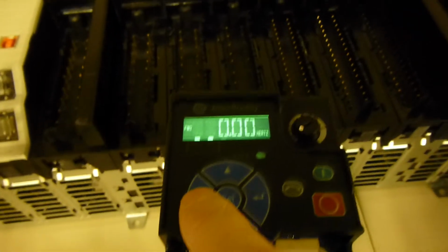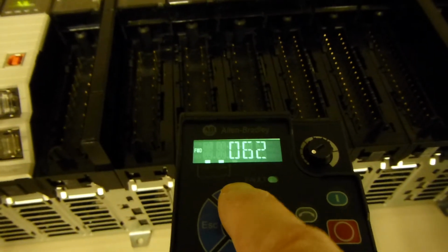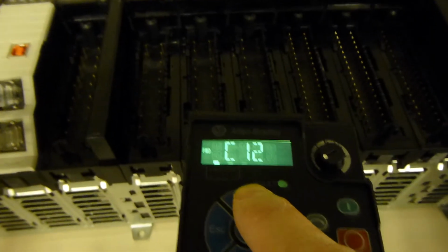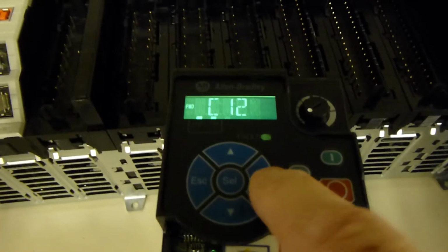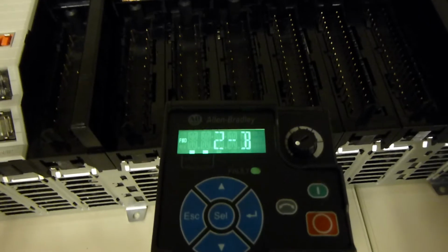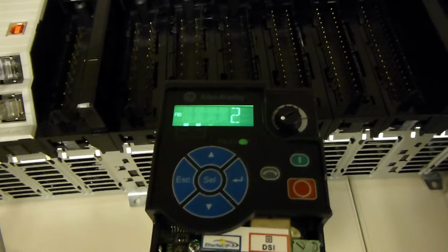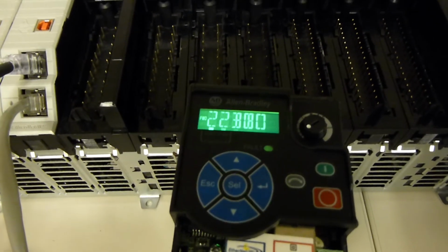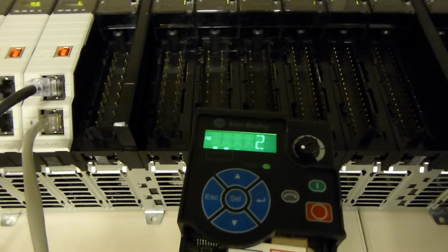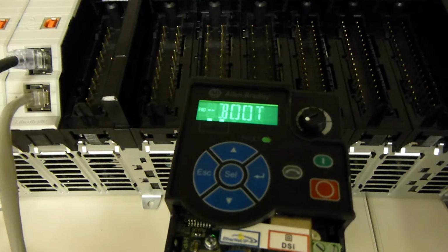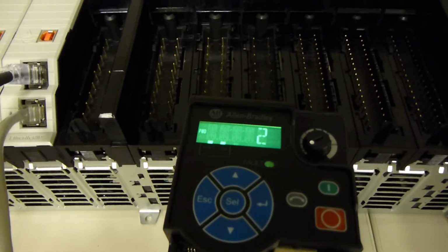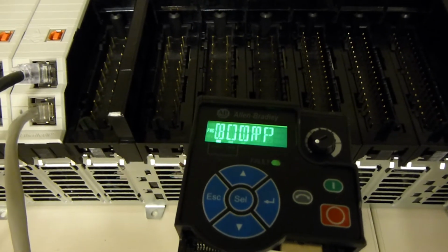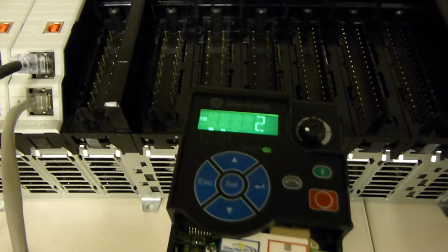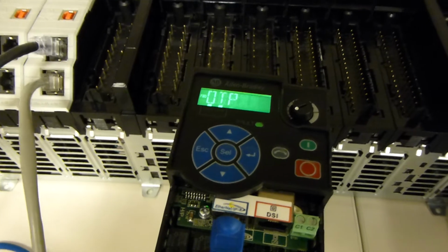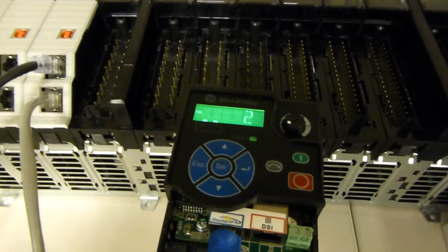So we're green there. Take a look at the drive. We're green. We can go back in just to verify our C128 change, and it's set for 2, which again says BOOTP, but we are using DHCP. Another feature of using DHCP is that you cannot verify what the DHCP-provided IP addresses are, each of the octets, in the online drive parameter space. There's no visibility on those, so it's one thing to be aware of that could possibly be addressed in a future firmware release.